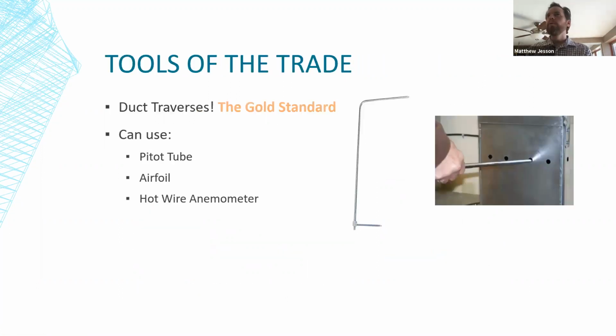So let's talk about how these are measured and what we use in the field. A duct traverse is hands down the best way to measure airflow. It is the most accurate. And what you can see on the picture there, how a duct traverse works is you drill holes in the duct, you insert a pitot tube, and you take multiple velocity readings with the pitot tube for each hole. Essentially what you're doing is creating a grid of velocity measurements. That is my dog shaking his collar. Sorry about the noise. So you give this grid that you're making of velocities across the area of the duct, and you average them out.